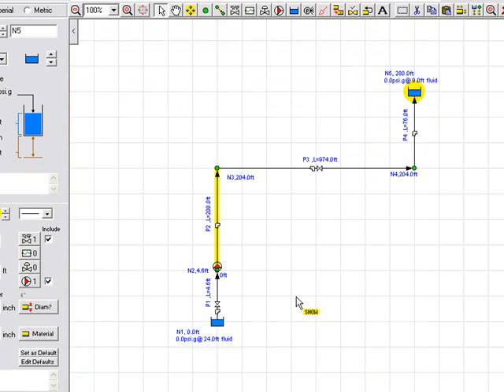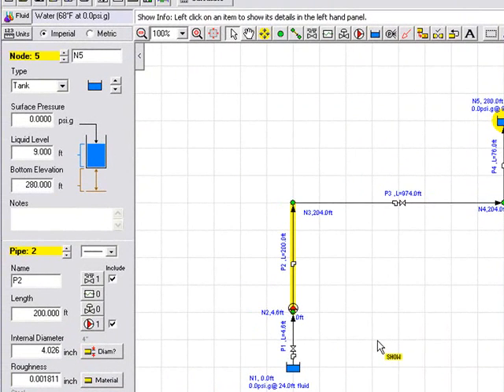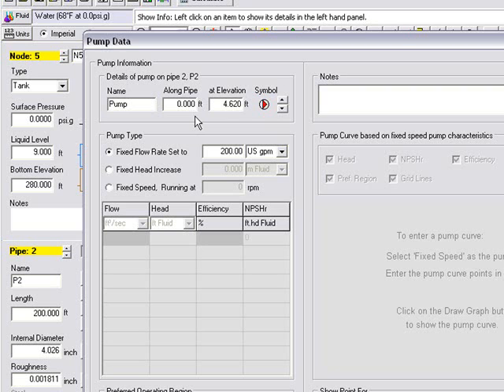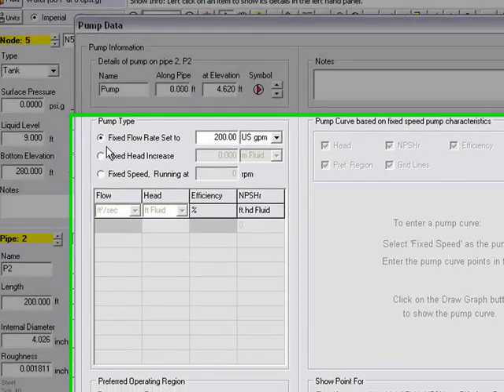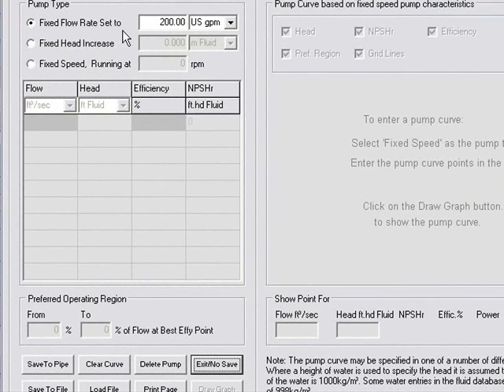Let's go ahead and run the calculation. Just before we do that, we can review the pump details. If we click on the pump, we can see that the pump is set to be 0 feet along the pipe at an elevation of 4.62 feet, which is the same elevation as the start of the pipe. Here we've chosen a pump type, which is a fixed flow rate. We're asking it to produce 200 US gallons per minute. What we want the calculation to do is to work out the pump head required to meet that flow demand.